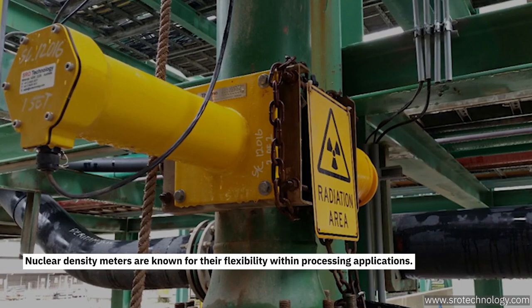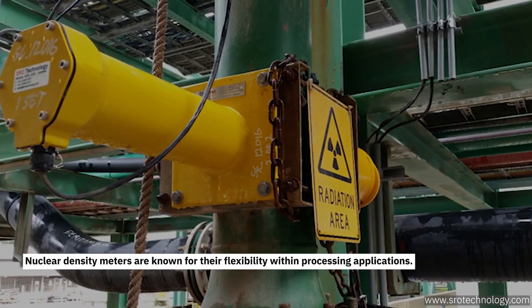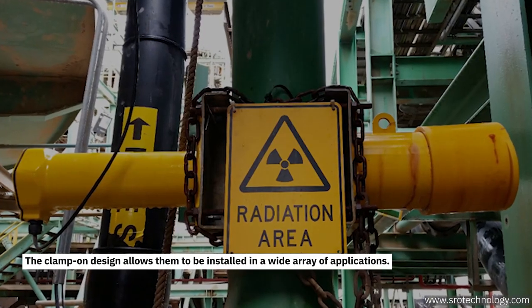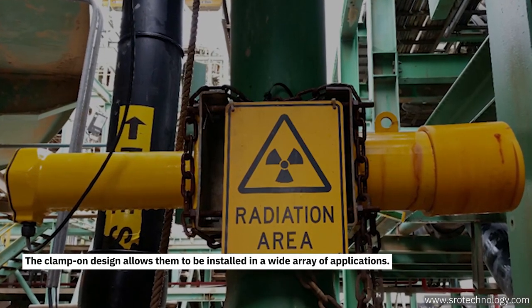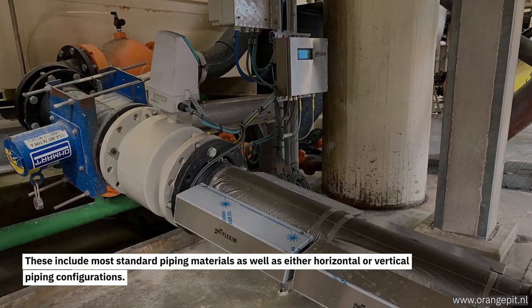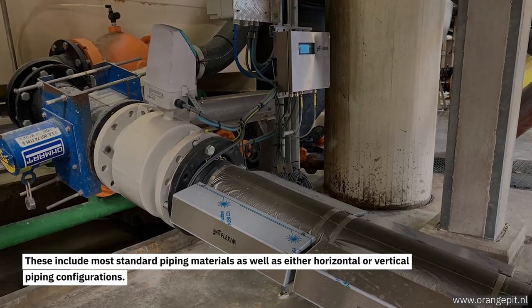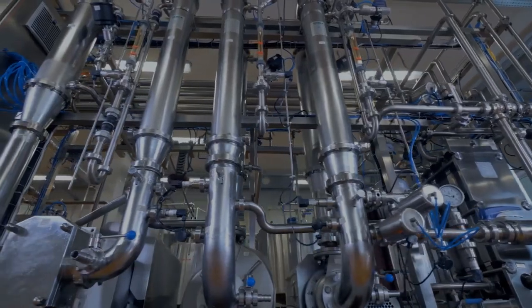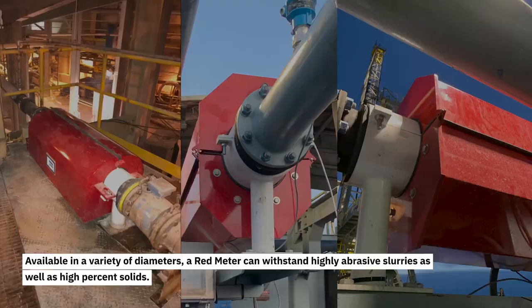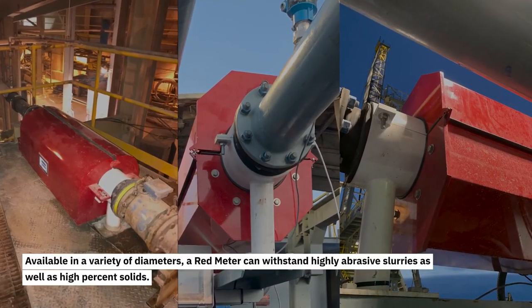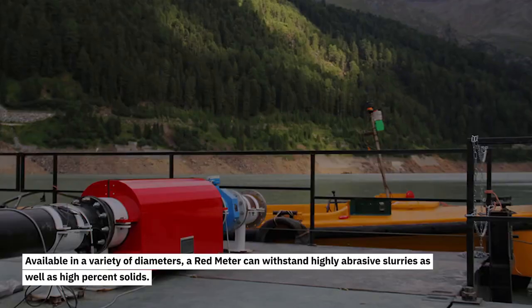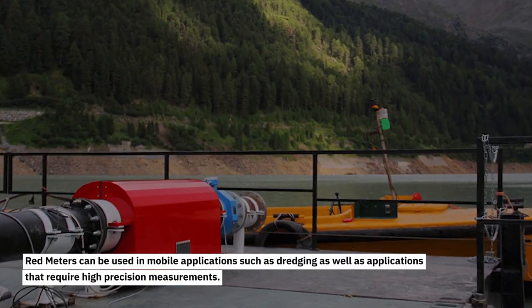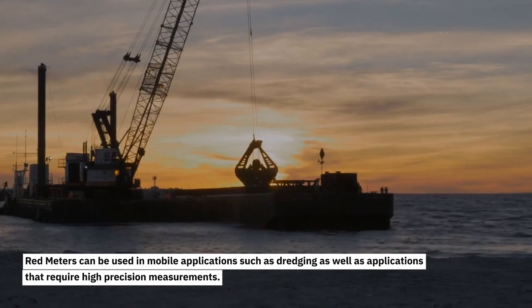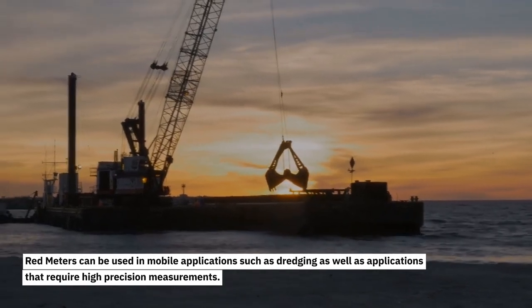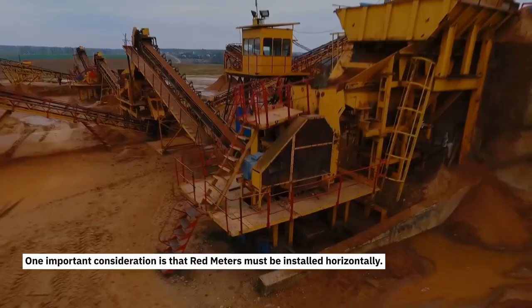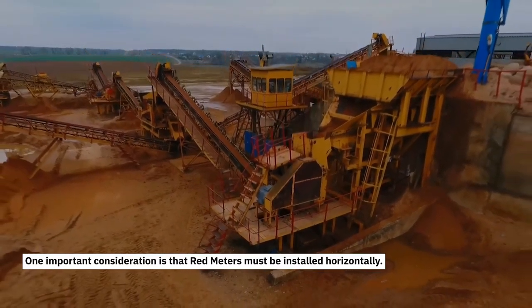Nuclear density meters are known for their flexibility within processing applications. The clamp-on design allows them to be installed in a wide array of applications. These include most standard piping materials, as well as either horizontal or vertical pipe configurations. Available in a variety of diameters, a Red Meter can withstand highly abrasive slurries as well as high percent solids. Red Meters can be used in mobile applications, such as dredging, as well as applications that require high precision measurements. One important consideration is that Red Meters must be installed horizontally.